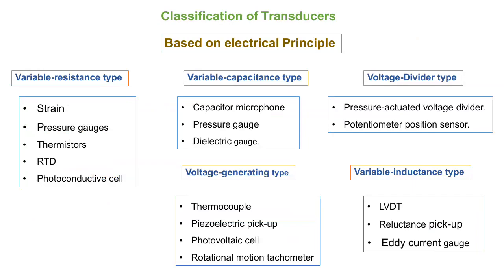One more classification is based on electrical principles. Almost all transducers can be classified by electrical principle since most transducers are based on electrical principles. Based on the electrical principle, there may be variable resistance type, variable capacitance type, variable inductance type, voltage divider type, and voltage generating type. Variable resistance type examples include strain gauges, pressure gauges, thermistors, RTD (resistance temperature detector), or photoconductive cells.